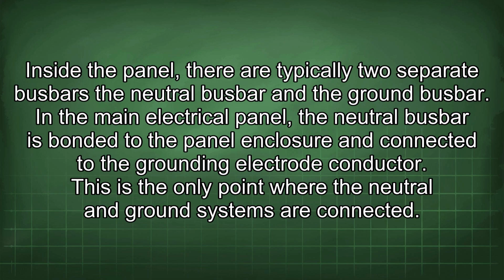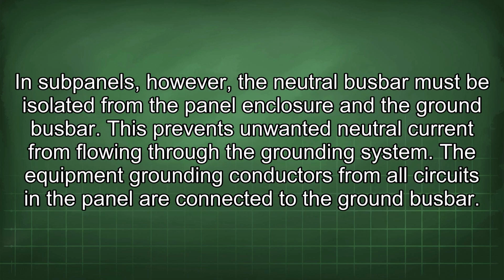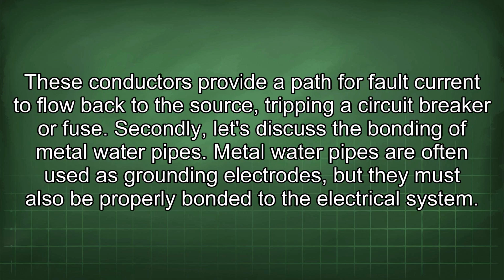This is the only point where the neutral and ground systems are connected. In subpanels, however, the neutral busbar must be isolated from the panel enclosure and the ground busbar. This prevents unwanted neutral current from flowing through the grounding system. The equipment grounding conductors from all circuits in the panel are connected to the ground busbar. These conductors provide a path for fault current to flow back to the source, tripping a circuit breaker or fuse.